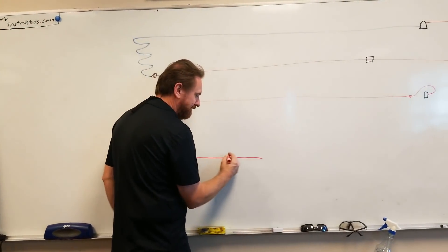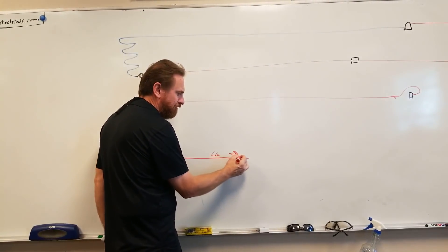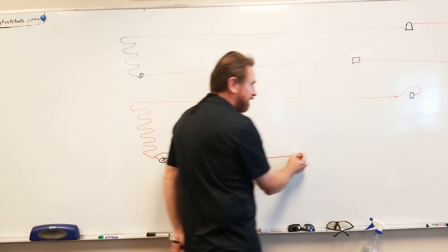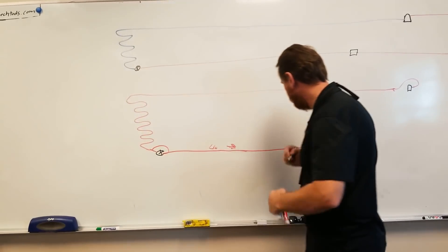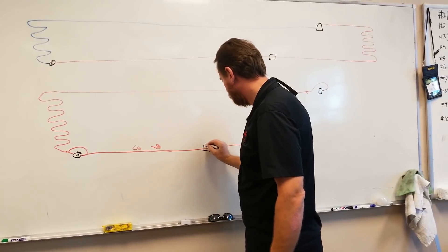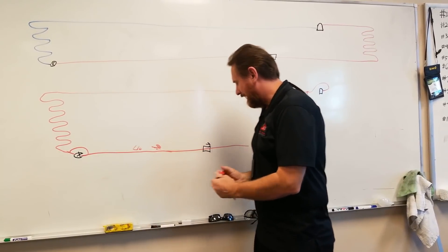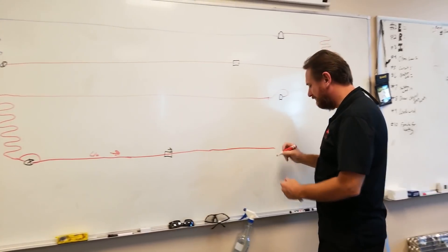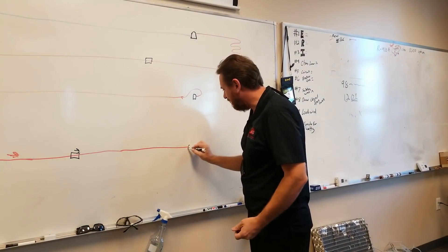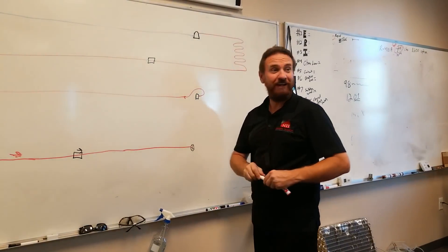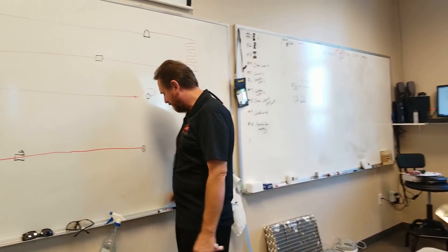This line here would be the liquid line, just going the opposite direction. I have to turn my filter dryer around so it faces the other way. And then out here on the outside unit, what if I added a metering device here? Same coil. If I put a metering device there, what happens to my pressure? It would drop — low temperature, low pressure.